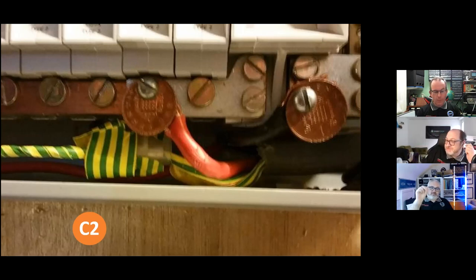If I see that picture, there is a risk of immediate danger to the homeowner, I go straight to C1. If I see that is a dodgy lash-up, where the person who did it just needs to be banned from the industry, then immediately it's potentially dangerous. It needs to be remedied. But if I'm not paid by the customer to do it, then the only thing I can do is discharge my legal duty of care as a skilled, competent person and hope that I keep records to argue in case the judge asks me why I didn't do it.